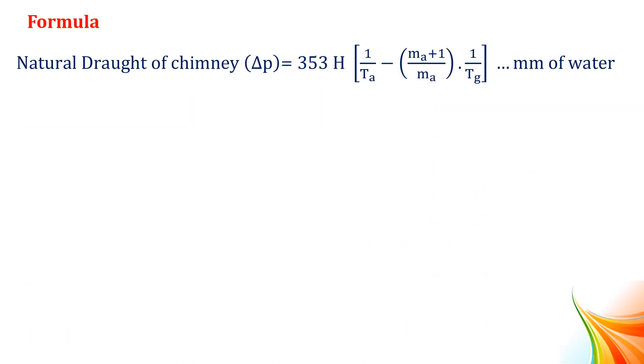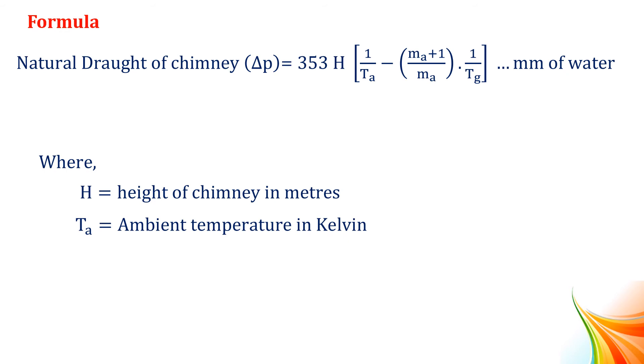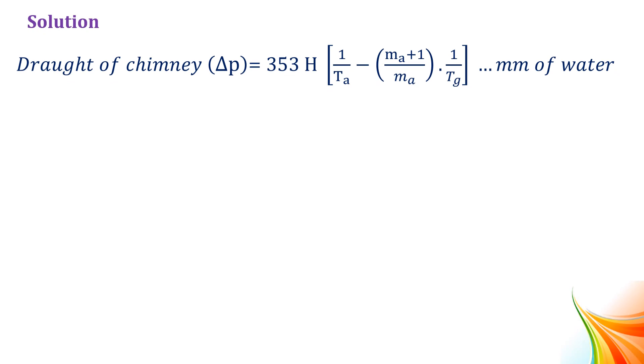Formula: The natural draught of chimney ΔP = 353H × [1/Ta − (Ma + 1)/(Ma × Tg)] mm of water. Where H is the height of the chimney in meters, Ta is the ambient temperature in Kelvin, Tg is the flue gas temperature in Kelvin, and Ma is the mass of air supplied per kg of fuel. Solution: ΔP = 353H × [1/Ta − (Ma + 1)/(Ma × Tg)] mm of water.